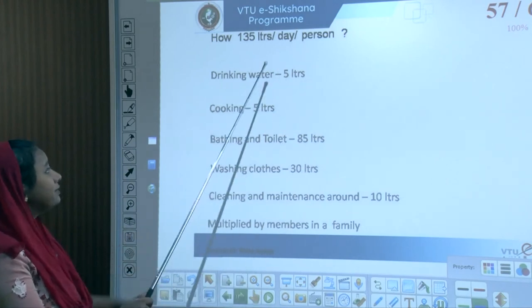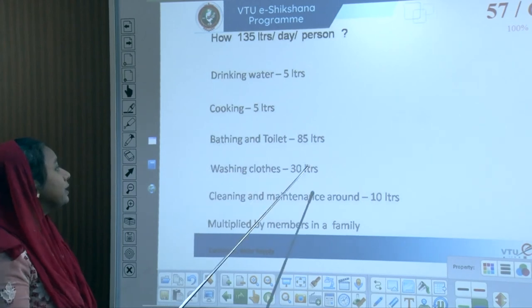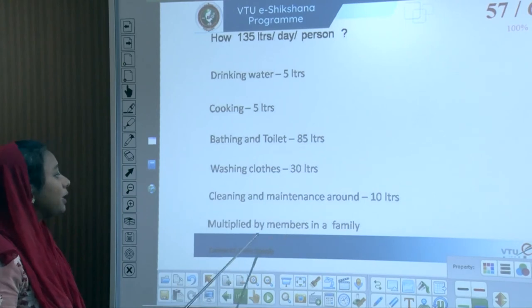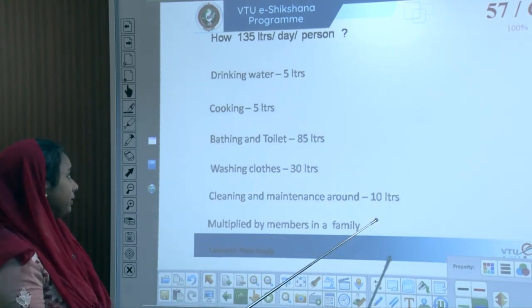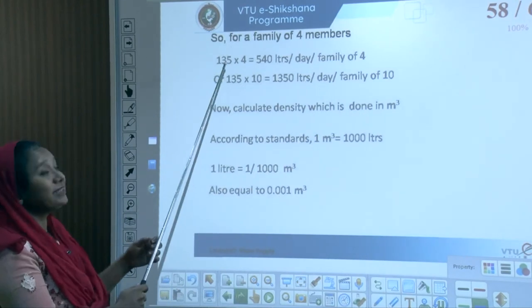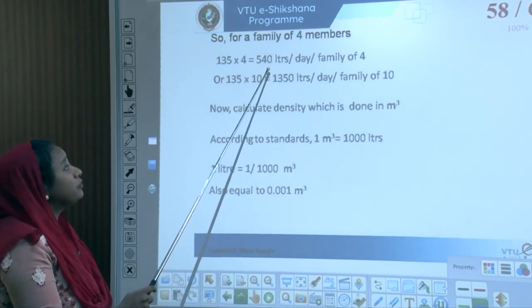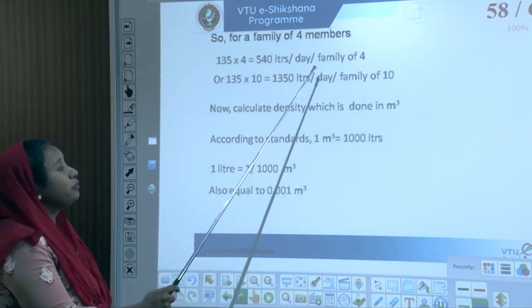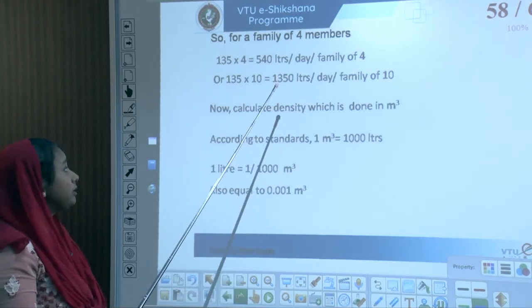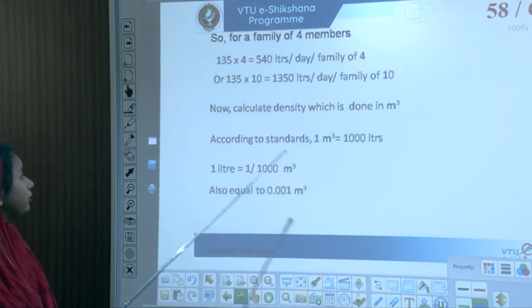The 135 litres per person per day breaks down as: drinking water 5 litres, cooking 5 litres, bathing 85 litres, washing clothes 30 litres, cleaning and maintenance 10 litres. Multiplied by family members: for a family of 4, 135 × 4 = 540 litres per day; for 10 people, 135 × 10 = 1,350 litres per day.